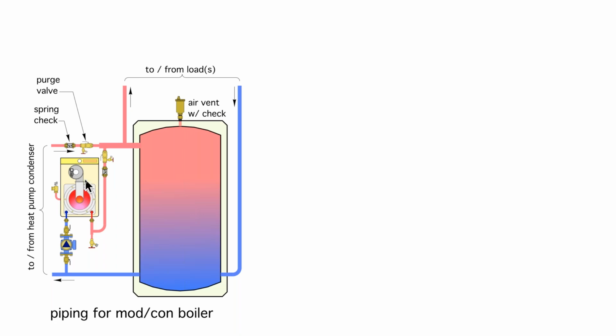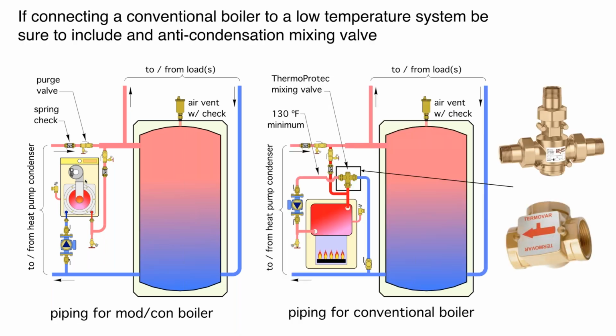This is a ModCon boiler. This can go right down to low water temperatures, and there's nothing detrimental that happens to the boiler. It's got a stainless steel heat exchanger, okay? It's designed to operate at low water temperatures. But I want to caution you, if you've got an existing system that has a cast iron boiler, a steel fire tube boiler, or a copper tube boiler, those boilers are not designed to operate with sustained flue gas condensation. So if you're going to use that boiler and you're going to connect it to a low temperature distribution system, perhaps you're taking what was originally a high temperature system and modifying it into a low temperature system, like we're going to talk about next week, we've got to protect that boiler against flue gas condensation.